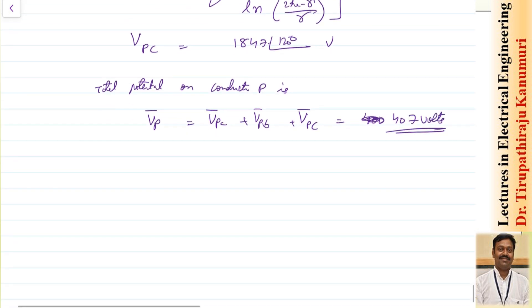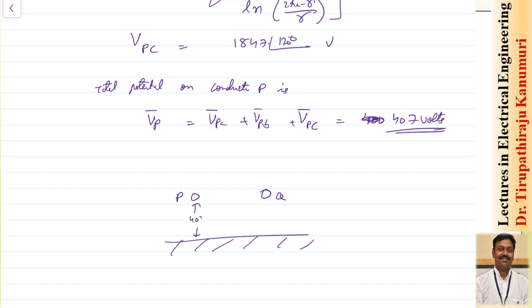The voltage is not nullified — 407 volts appears on the communication line conductor P with respect to ground. Similarly, some voltage V_Q appears on conductor Q. While the potential difference V_P minus V_Q between the two conductors may be manageable, each conductor is raised above ground potential. If a person touches conductor P they will experience a shock. So proper insulation must be provided to withstand this voltage, and transposition measures must be taken to nullify it — as discussed earlier.